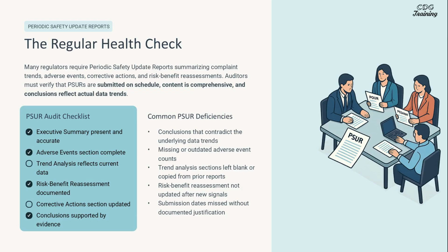Field safety corrective actions must be timely and well documented. Global coordination and verification are crucial when post-market data indicates a serious issue. Periodic safety update reports are essential for summarizing complaint trends and risk assessments. Auditors must ensure these reports are timely and accurate.